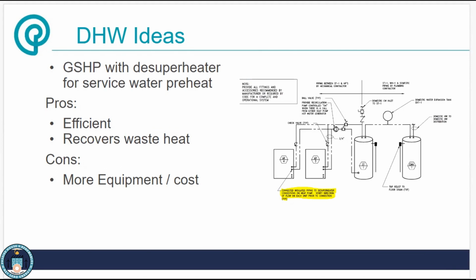So with a lot of the projects trying to electrify a DHW setup, you've got a need to hit that water heating set point of about 140. A lot of heat pump based water heating equipment on the mechanical end of things can't necessarily do that. So we'll see either this post heating tank like they've used on this project, or we've also seen people use a water to water heat pump in series with another water to water heat pump. So we've got an ability for it to boost temperature even further as they're built up in series.